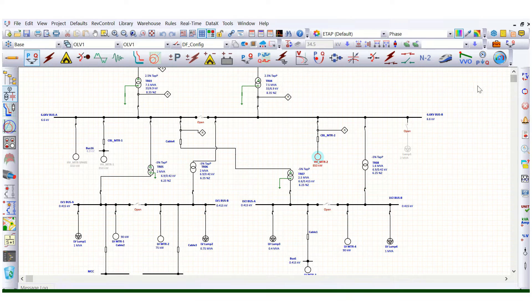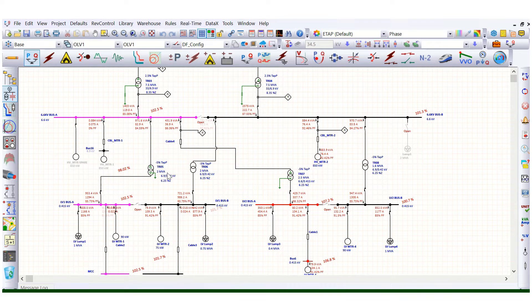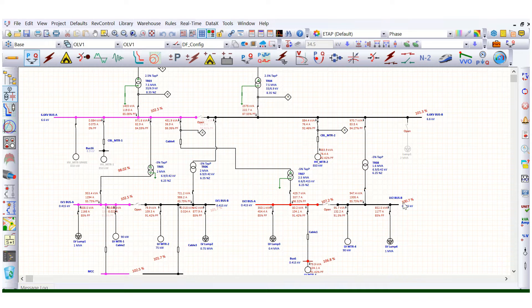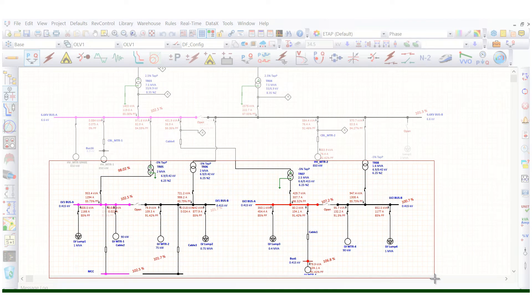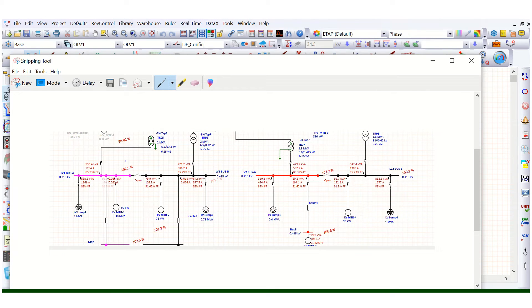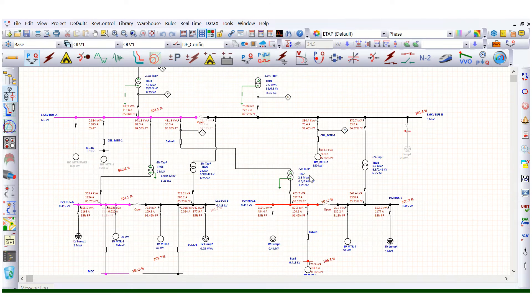Now let's run this load flow analysis and check the voltage levels. You can see this is 102.5 percent, this is 101.7 percent, this is 107.2 percent, and this is 100.7 percent. Let's take a snapshot of these results under this condition.